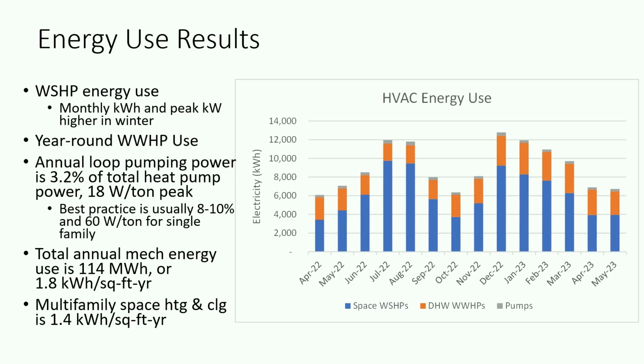It turns out energy use in this building was very good and very low. And you can see the mix. So blue is what the space heating heat pumps use, the water source heat pumps. Orange is what the domestic hot water system used. And the green that you almost can't see is the pumping power. And of course the water heating, the water-to-water heat pumps for domestic hot water, ran all year round, and they extracted heat from the loop the entire time, and we'll get into that a little more.